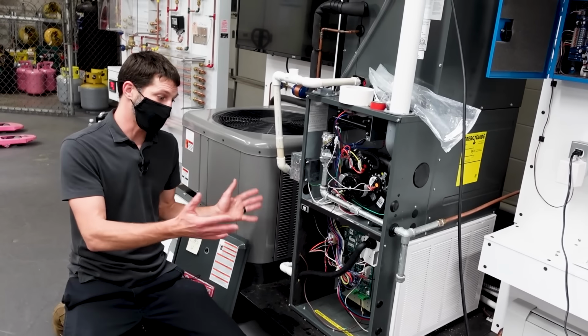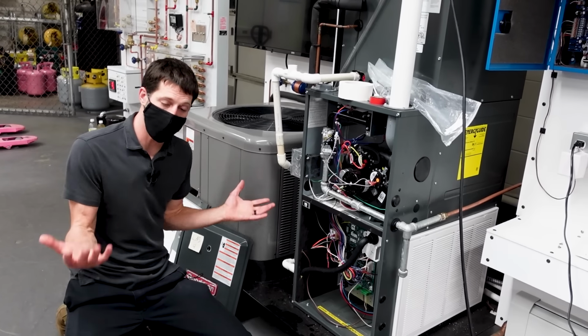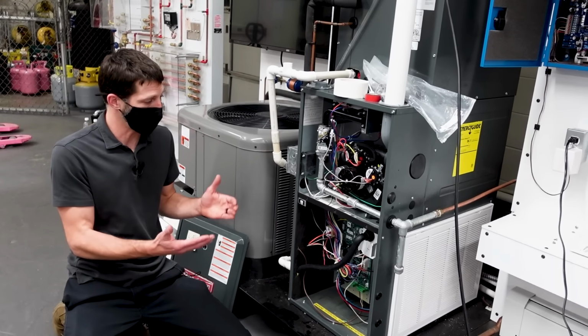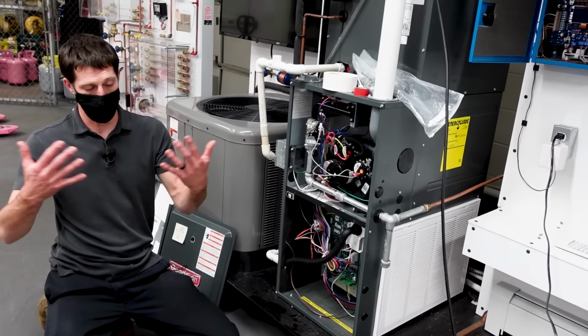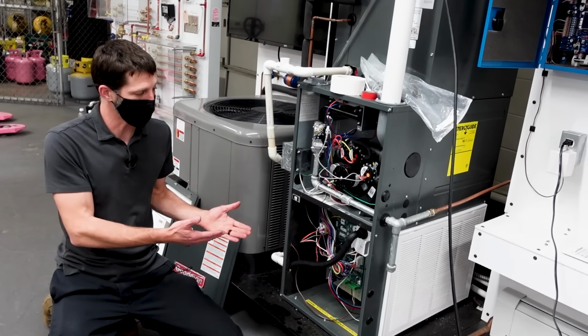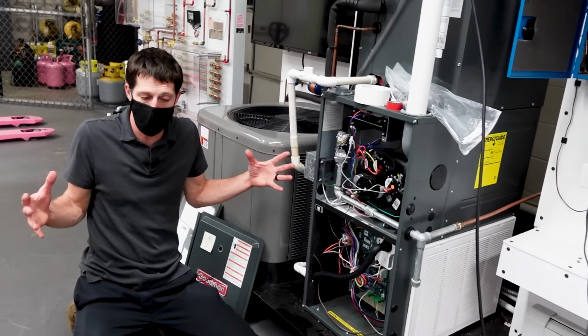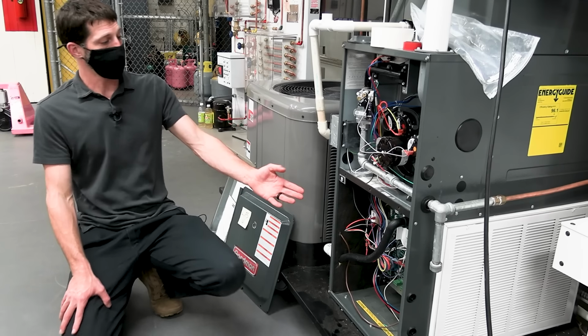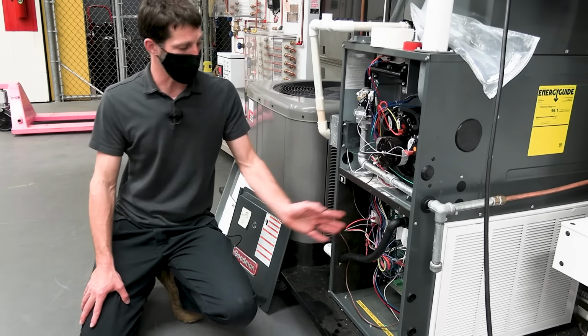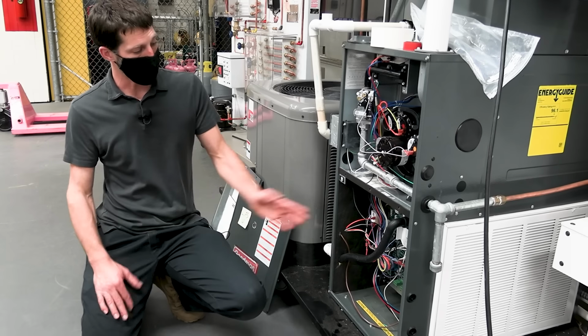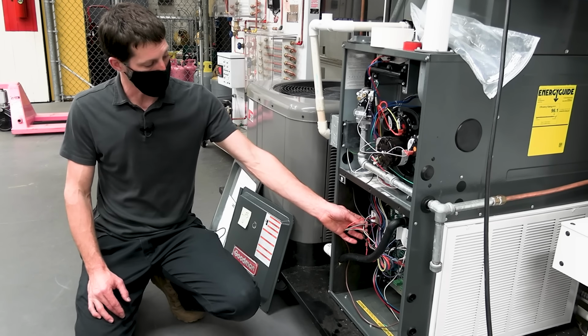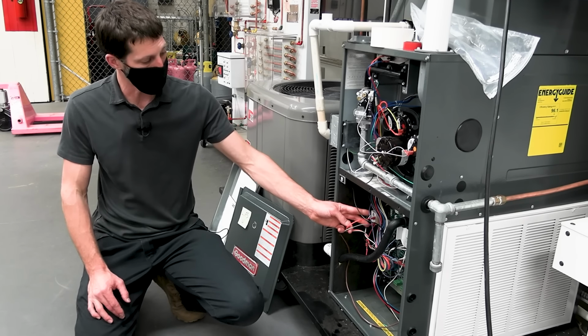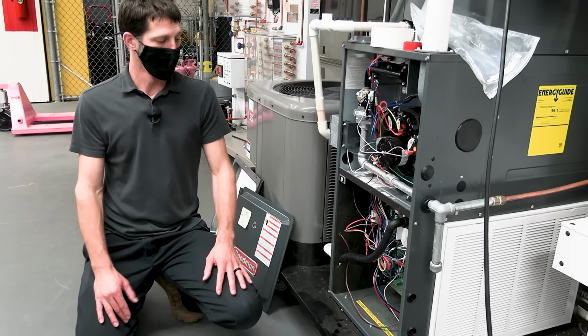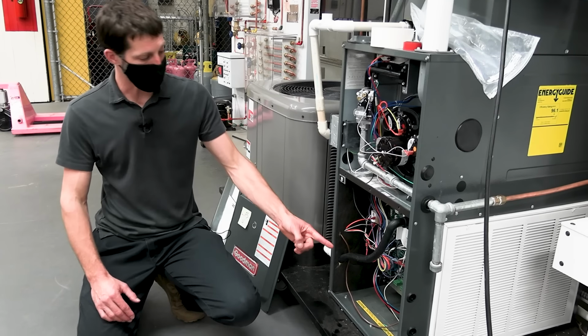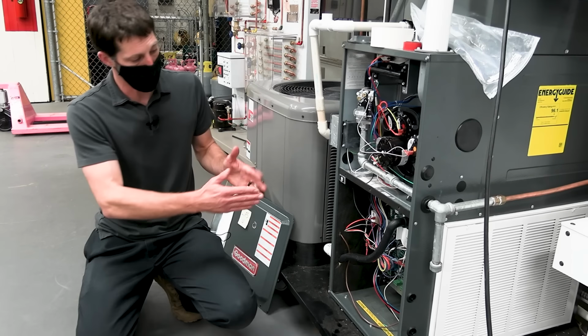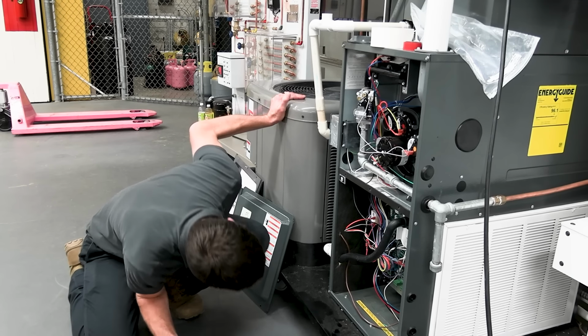If you have an outdoor package unit, the package units cannot be any higher than 80% efficient because you'll have a condensate line on them, and obviously it's low temperature outside, so that condensate line would freeze. So those ones are basically stuck at 80. You may have in your service truck a multi-tap transformer that's good for 240 volts, 208, 120. It's got multiple leads on that for the input, the alternating current, and on the other side you have 24 volts, which anytime you measure between R and C, after the power goes through the fuse, there's usually a 3 amp or 5 amp fuse.